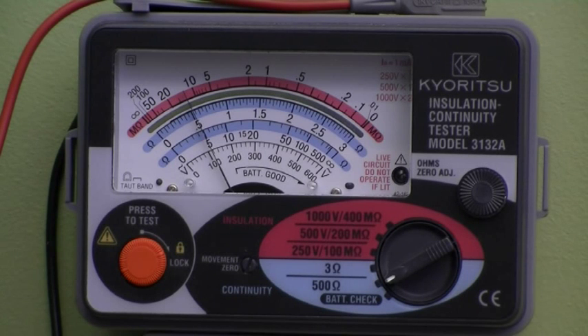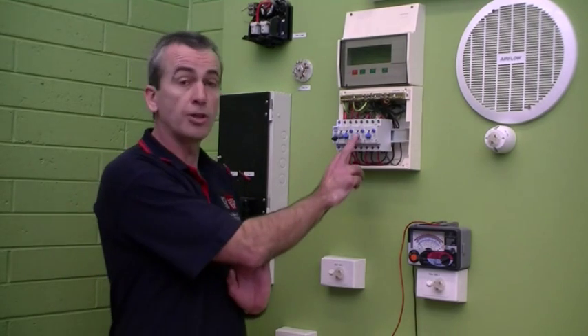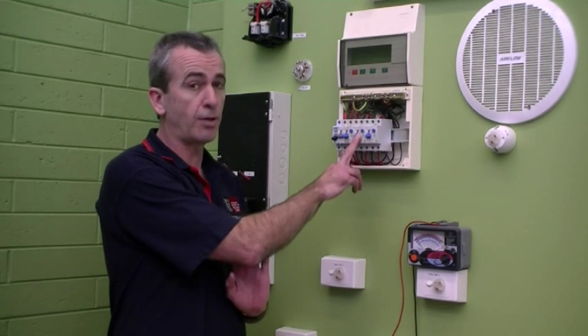So there is a fault in the earthing system here that I'll have to repair before supply can be connected to the installation. It's important you always do your earth resistance test to ensure that there is very low resistance on the earthing system, so that when the installation does have supply connected to it, if there is a fault from an active to an earth, the low resistance of the earthing system will make sure that there is a very high value of current flow to make sure the circuit breakers operate to isolate the fault from the supply.